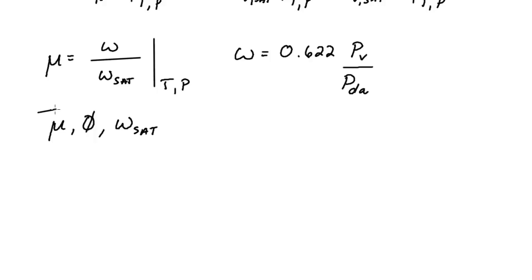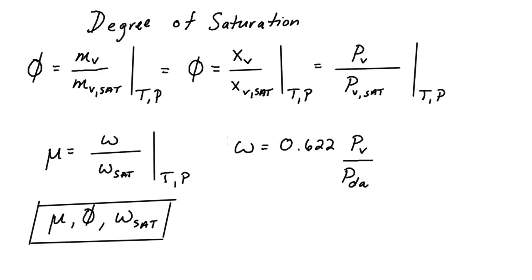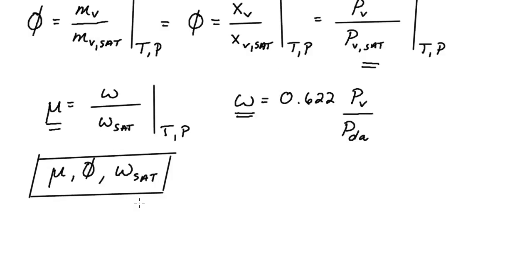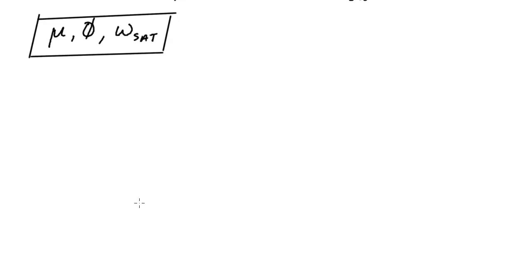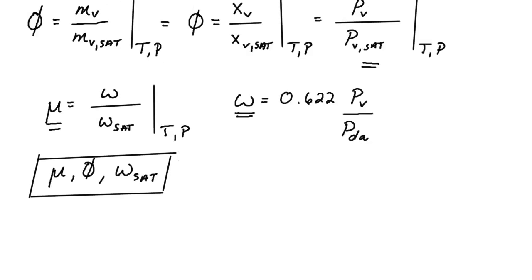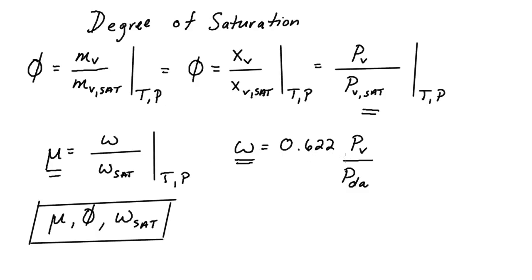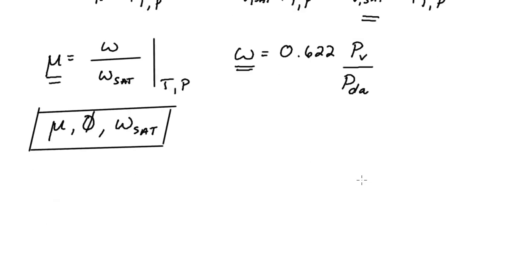We want a useful relationship between mu, phi, and omega saturation. We'll combine the equations, starting with pressures. This is covered in ASHRAE Fundamentals, but they glaze over how it's done, so it's a useful exercise to go through the algebra. Let's begin with the humidity ratio and replace the partial pressure of dry air with the total pressure. So omega is equivalent to 0.622 times the partial pressure of the vapor divided by the total pressure minus the partial pressure of the vapor.